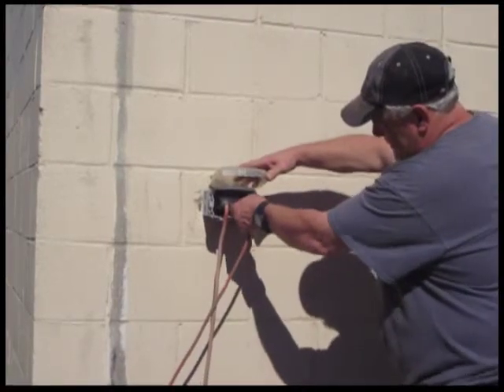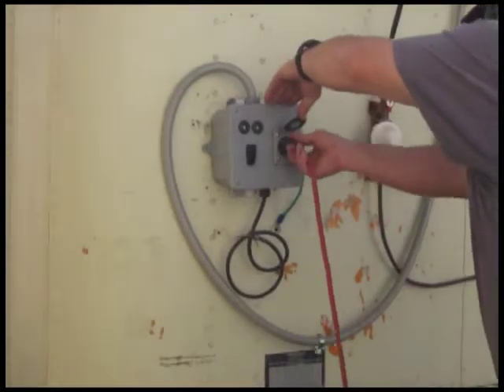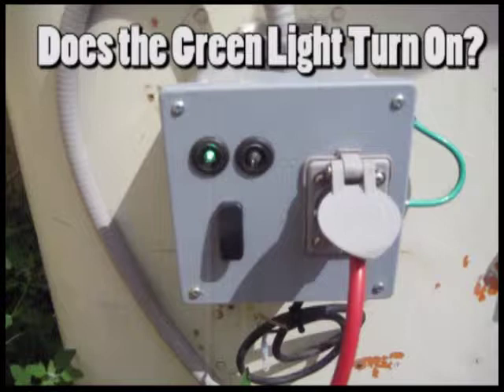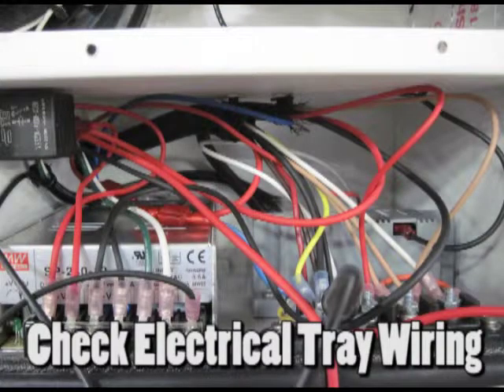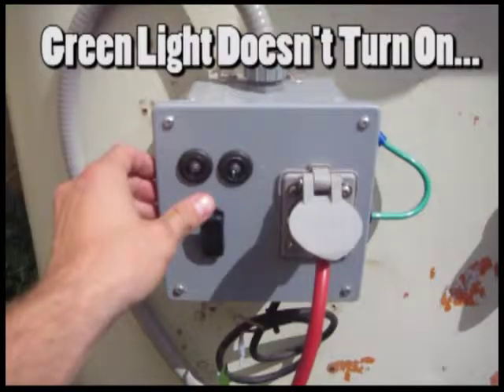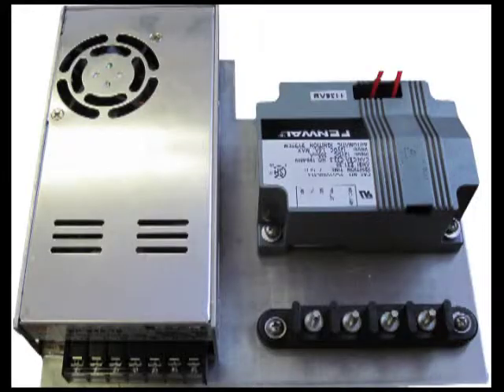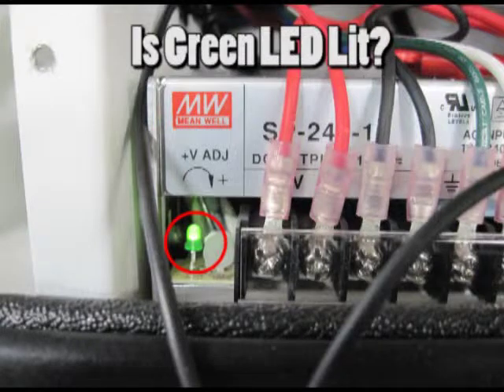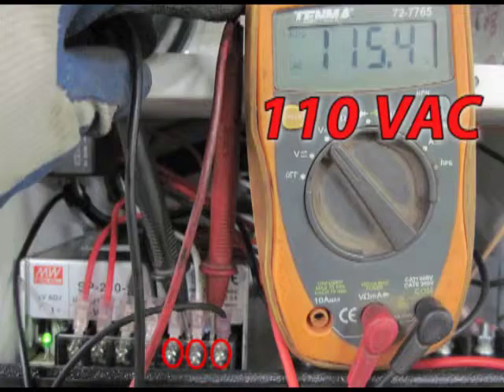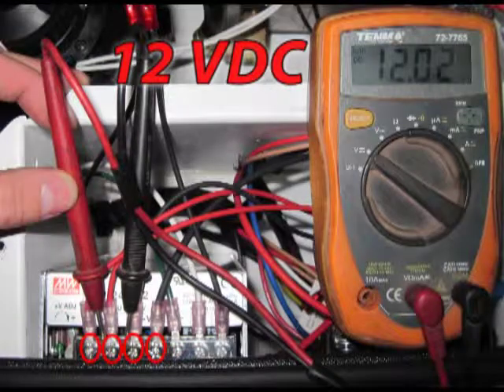Plug in the 110 VAC power supply and restore power to the heater. If the green light on the control box comes on momentarily, carefully check the wiring in the heater for loose connections. If the green light on the control box never comes on, check the power supply. Check to see if the green LED on the power supply is lit.